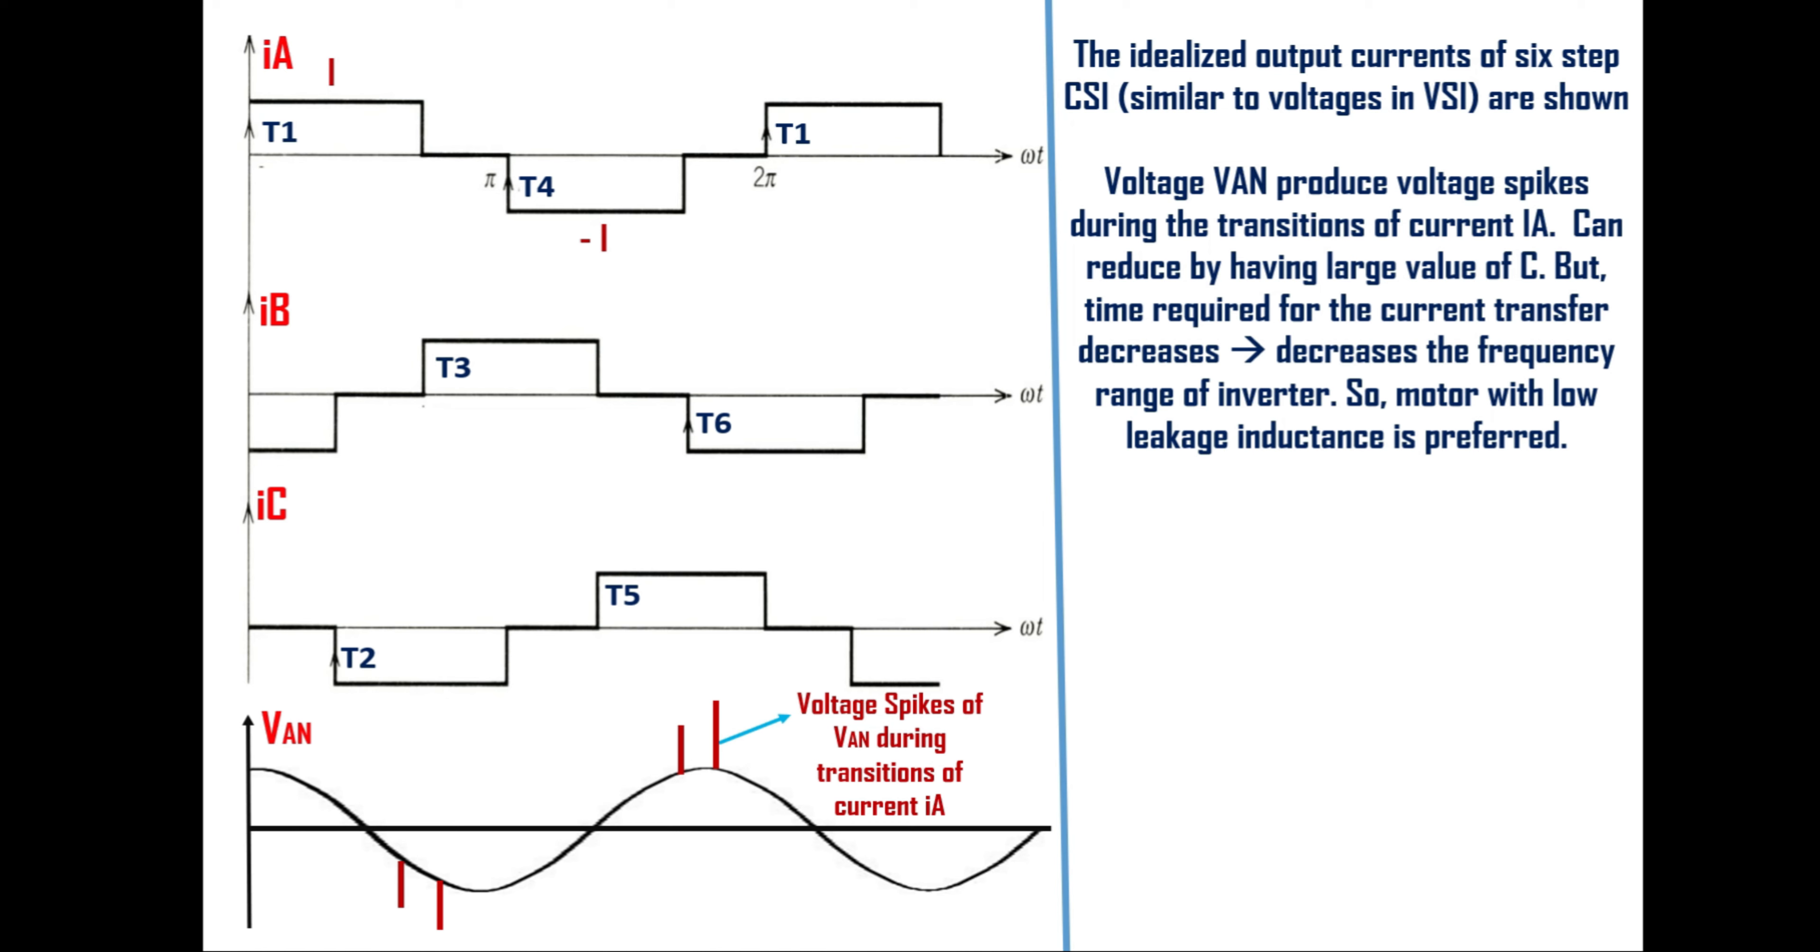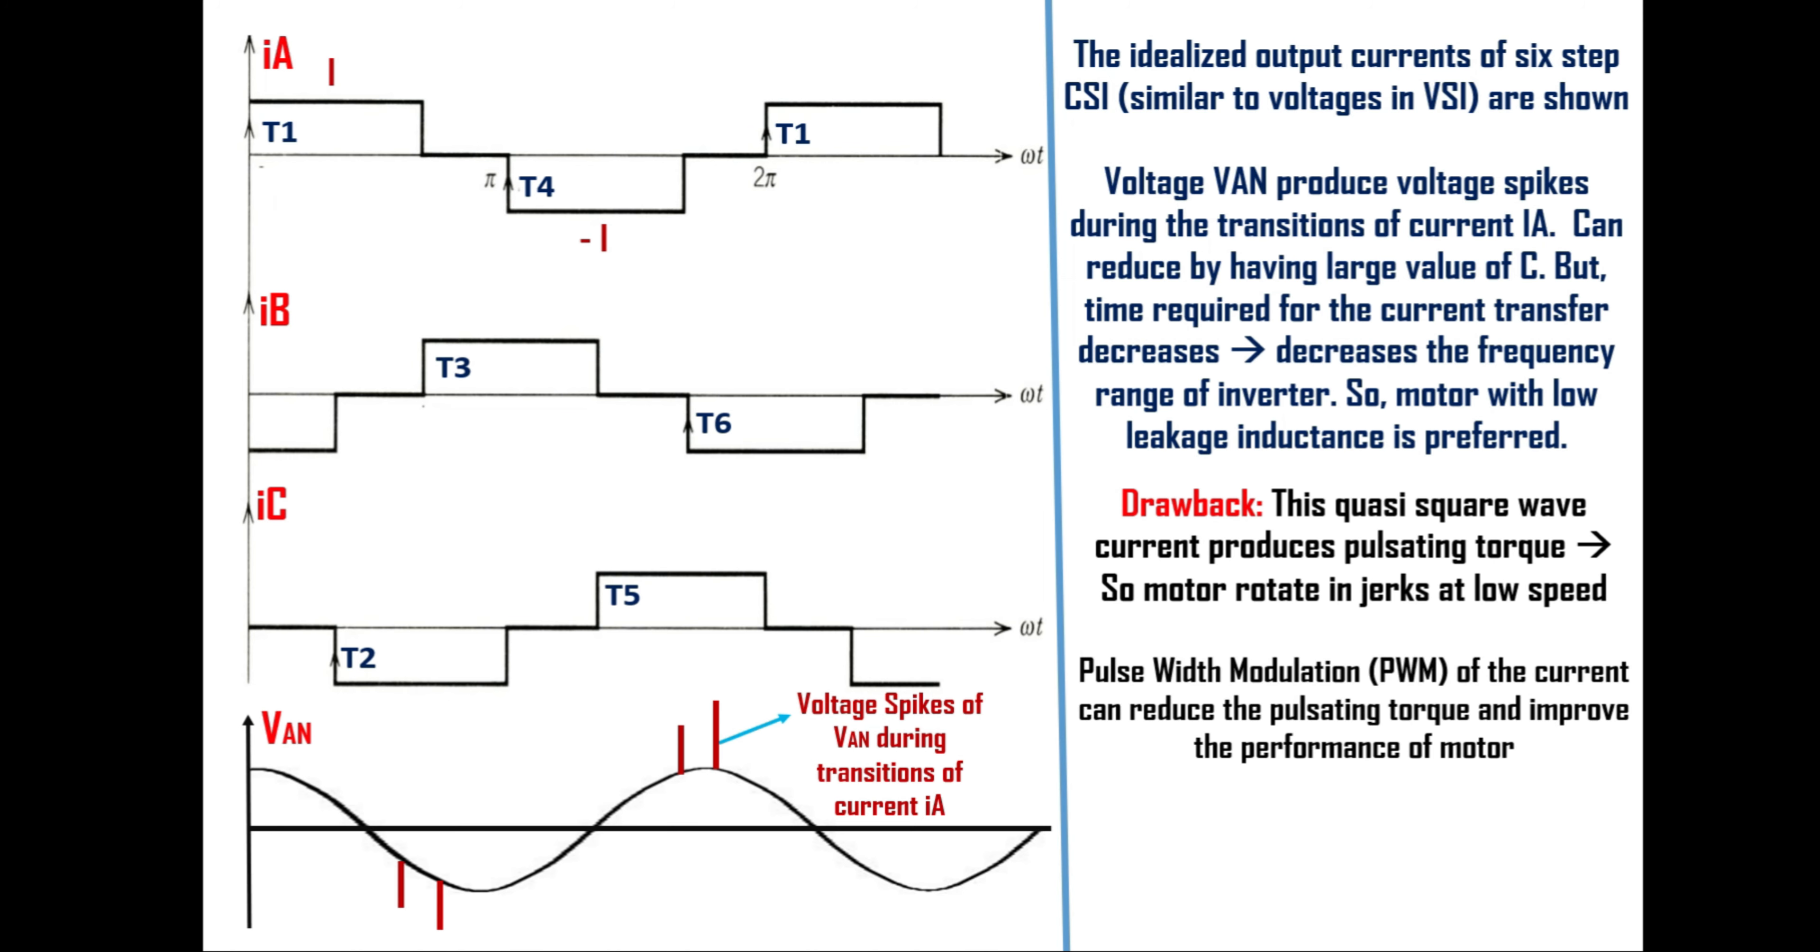The drawback of current source inverter is its quasi square wave current waveform. This current produces pulsating torque and motor will rotate in jerks at low speed. To overcome this pulse width modulation of current can be used. This can reduce the pulsating torque and also it can improve the performance of the motor. To understand the pulse width modulation of current source inverter please refer this IEEE paper.